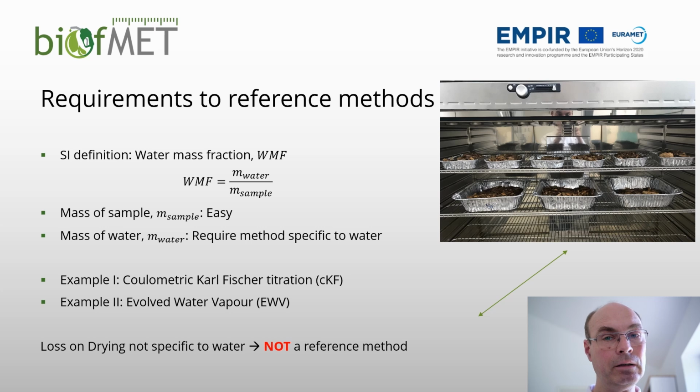Loss on drying is not a traceable method because you don't know whether all the weight loss is coming from water loss, or maybe there are some organic volatile compounds that are also evaporating. That said, loss on drying usually gives quite good results on biofuels.